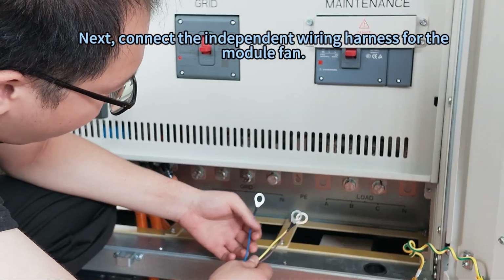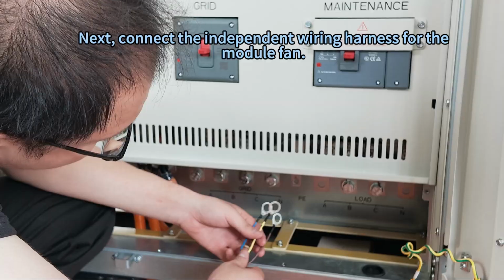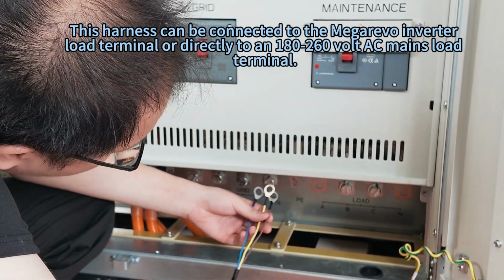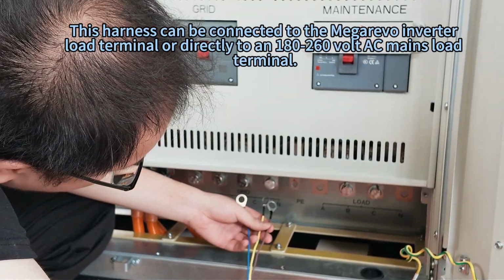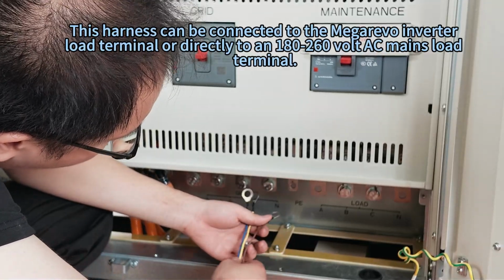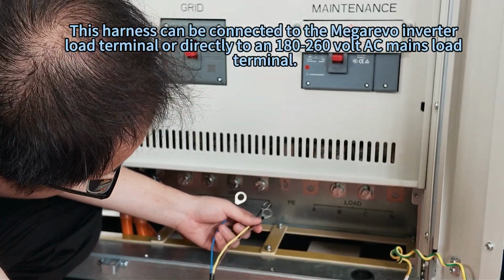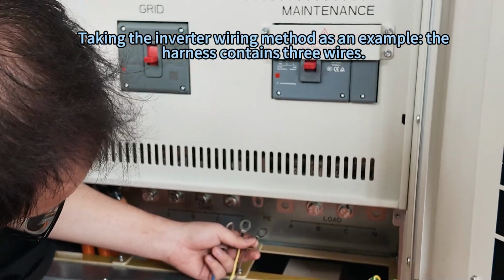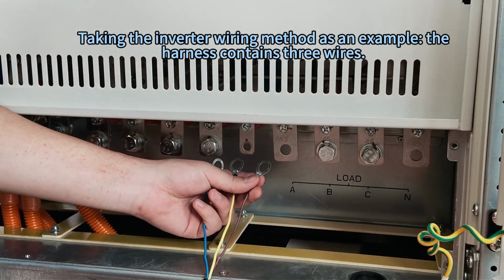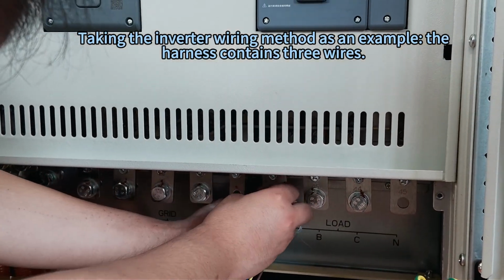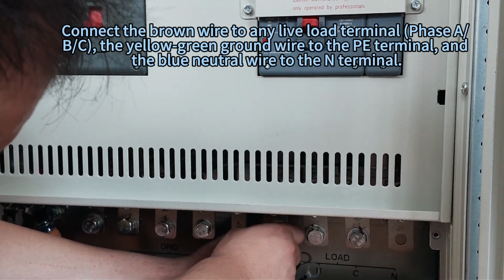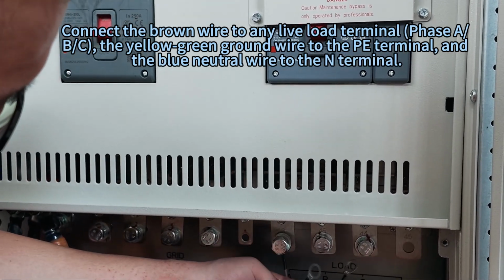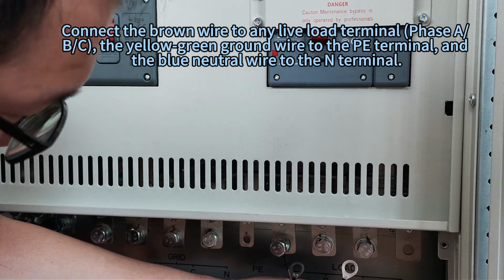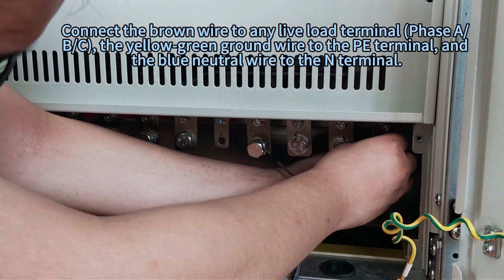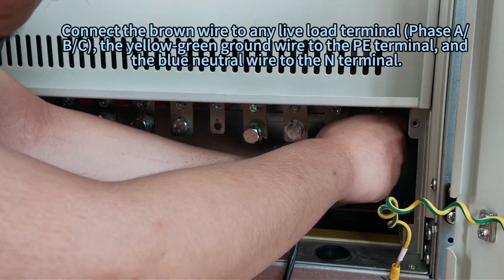Next, connect the independent wiring harness for the module fan. This harness can be connected to the Megarevo inverter load terminal or directly to an 180-260 volt AC mains load terminal. Taking the inverter wiring method as an example, the harness contains 3 wires. Connect the brown wire to any live load terminal phase ABC, the yellow-green ground wire to the PE terminal, and the blue neutral wire to the N terminal.